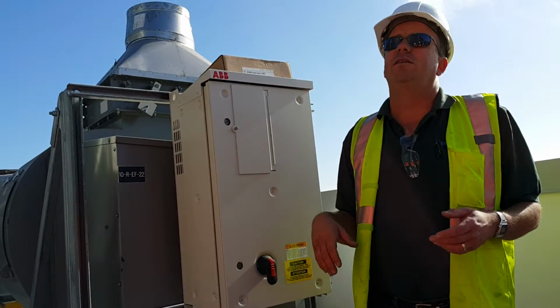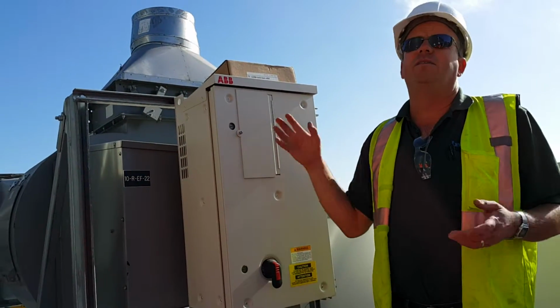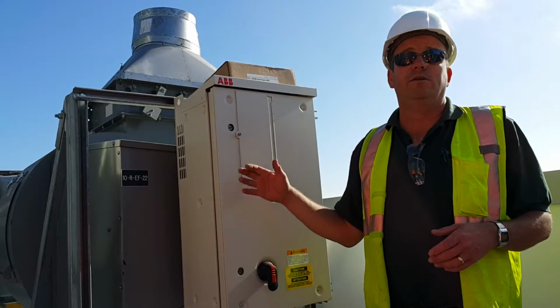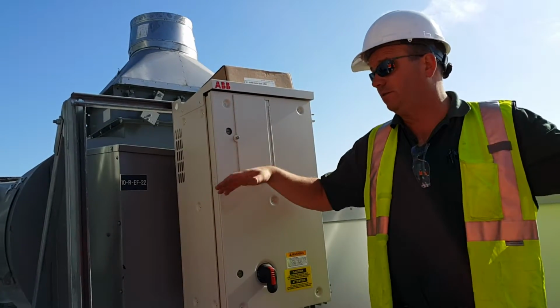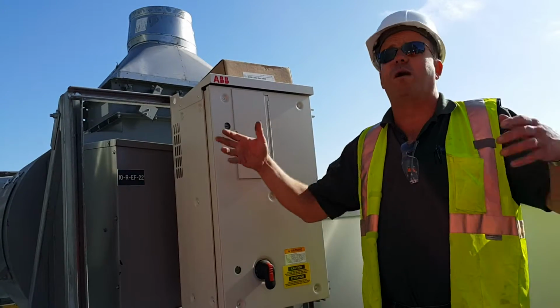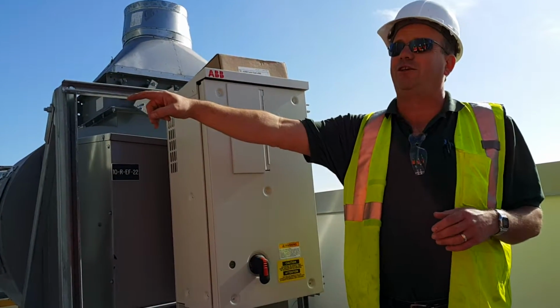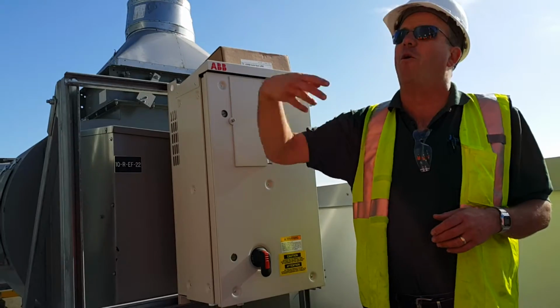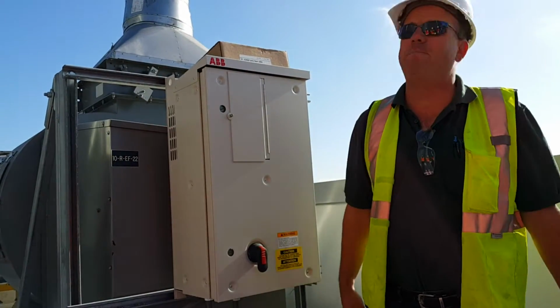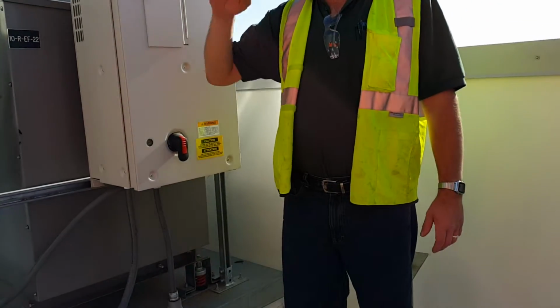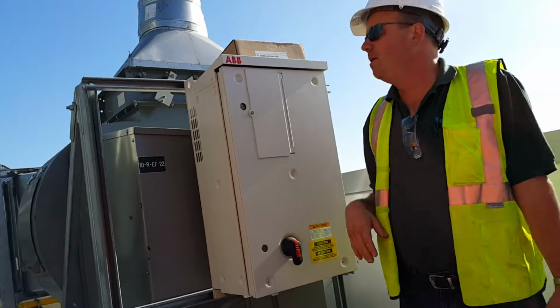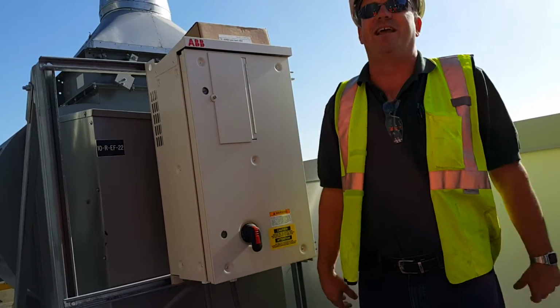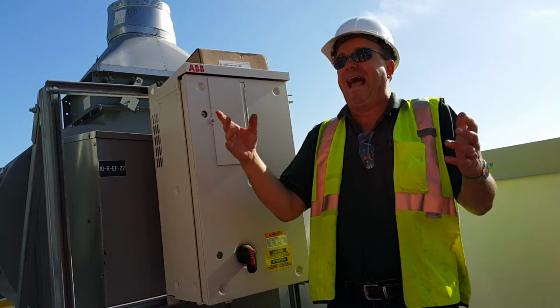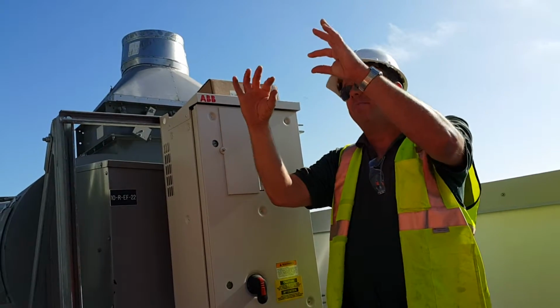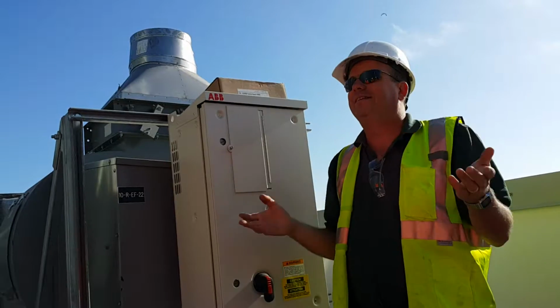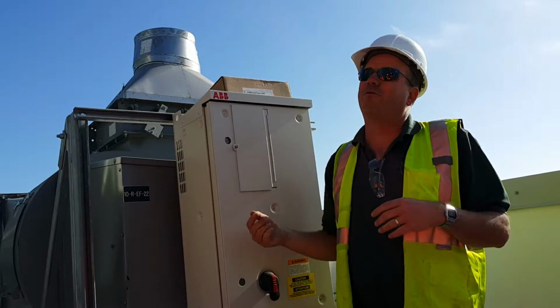But there's certain ones. Let's say, for example, in some cases we don't want to use the hand button. We use these things, this size, this model, 300 horsepower on a chiller. We don't want somebody to put that chiller in the hand and run that chiller motor without the oil and all the interlocks that the chiller has, right? So you turn the ability to put it in hand off. If you hit hand, it'll say alarm, button disabled. Well, that's not an alarm. People freak out like that. They see it says alarm very big and the number, and right down below it in smaller print, it says what it is, but they see that flash alarm, they go running for the hills.